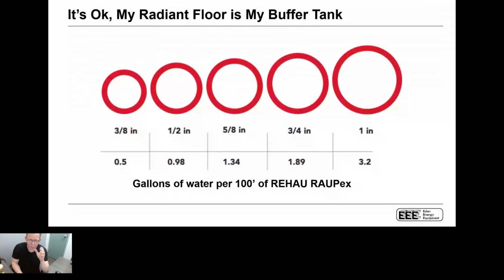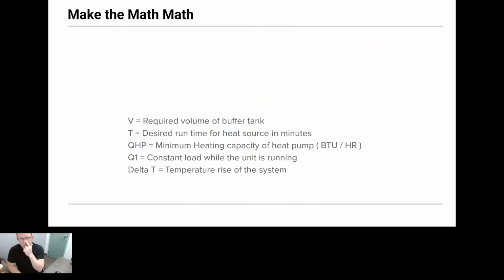The last thing on buffer tanks that I want to point out, and this does come into play, is people say, hey, why can't I just use my radiant floor as my buffer tank? Well, the reality is you can, but how much tubing do you have? You need to understand that when you look at half-inch tubing per 100 feet, you've only got like less than 1 gallon of storage within that space. And if you look at how much storage you actually need, well, depending on whether you're at design or not at design, it can make a huge impact.